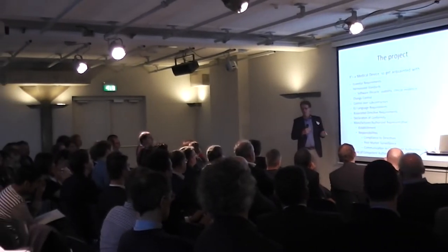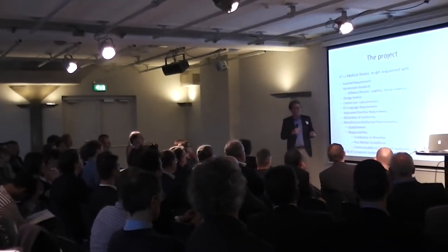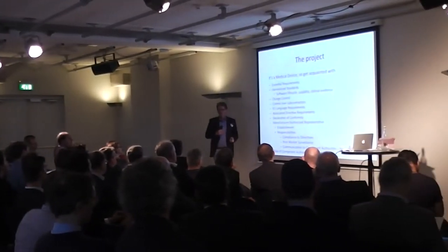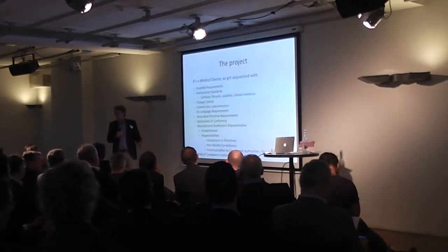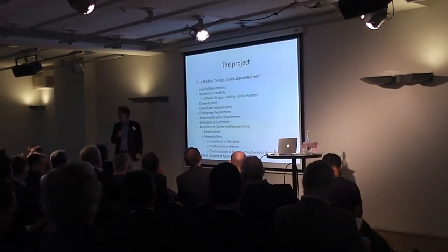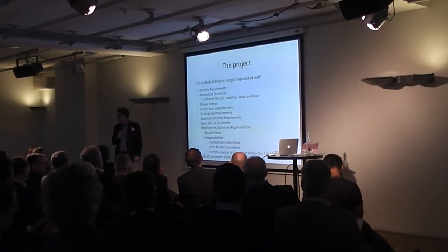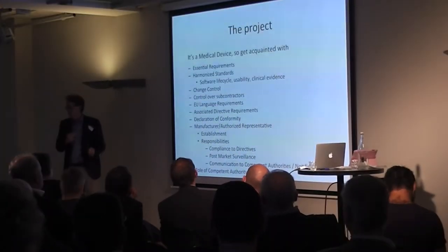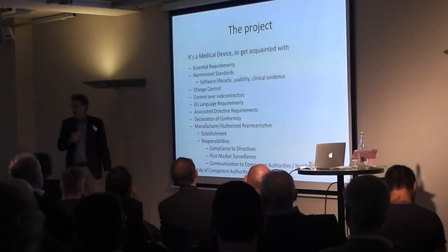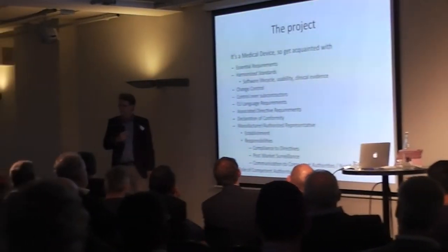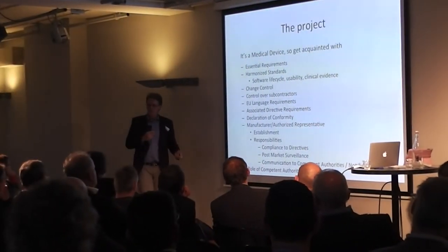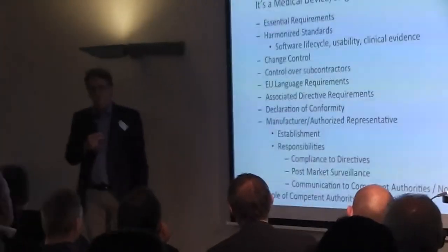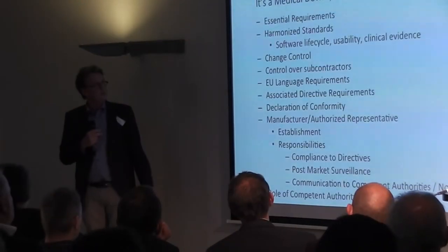It could be IEC 62304, and usability standards. But also clinical, because your device has a clinical functionality. So you need to substantiate that the claims are actually made. You can build the software and market it, but does it do what you need it to do? How do you validate that?